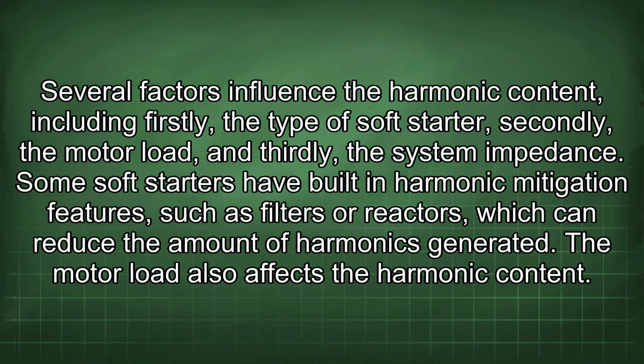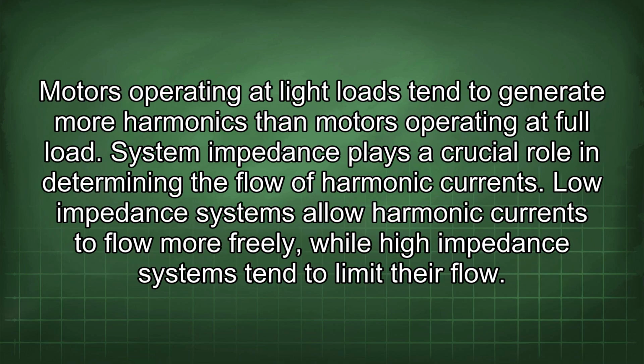This analysis involves measuring or estimating the harmonic currents present in the system and then calculating the required neutral conductor size. Several factors influence the harmonic content, including firstly, the type of soft starter, secondly, the motor load, and thirdly, the system impedance. Some soft starters have built-in harmonic mitigation features such as filters or reactors, which can reduce the amount of harmonics generated. The motor load also affects the harmonic content. Motors operating at light loads tend to generate more harmonics than motors operating at full load.